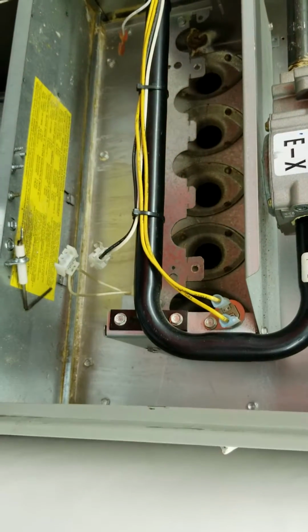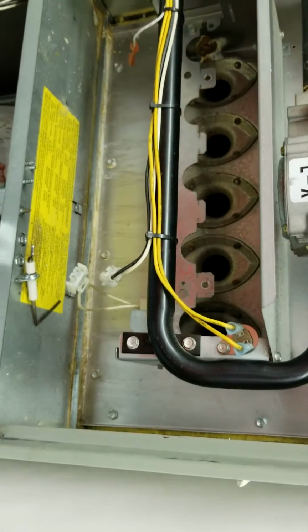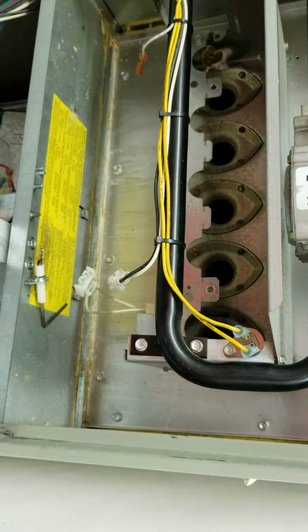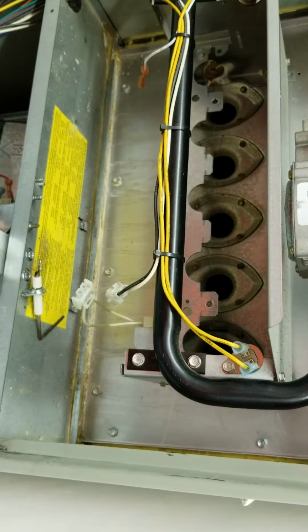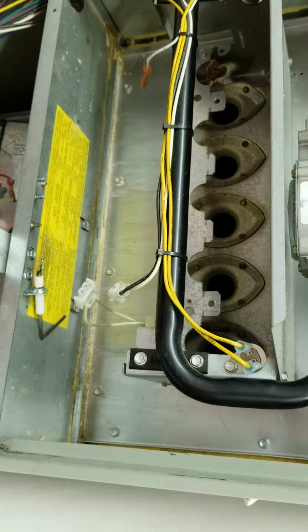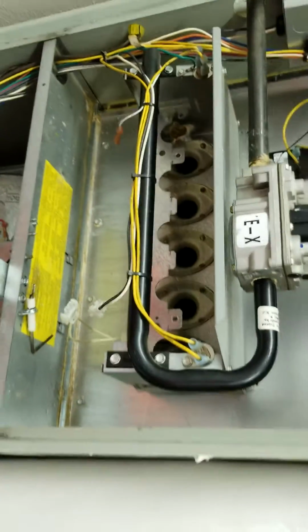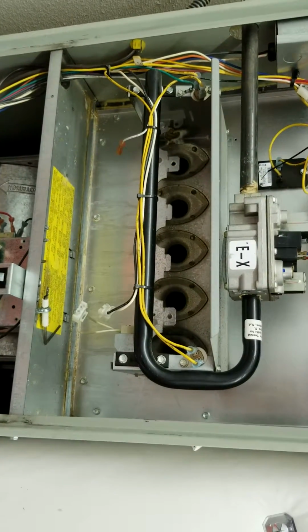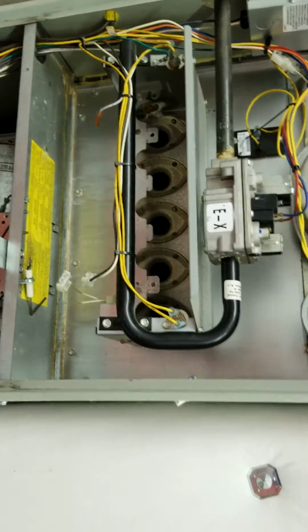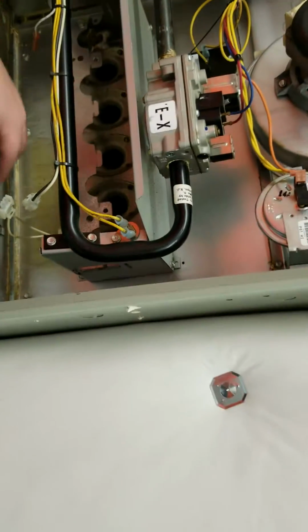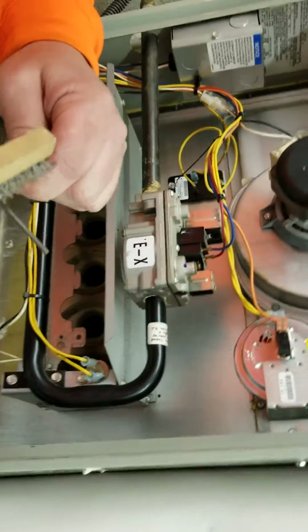This is for a carbide igniter. A nitride igniter will read significantly different, usually on the order of 15 to 20 ohms. So, okay, now you've got that. You're going to want to clean your sensor rod and clean your burners. Clean your burner sensor rod there.